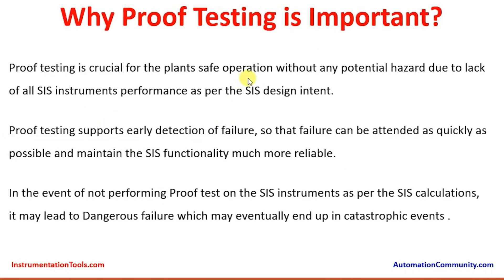Why is proof testing important? Proof testing is crucial for the plant's safe operation without any potential hazard due to lack of Safety Instrumented System performance as per the SIS design intent. Proof testing supports early detection of failure so that failure can be attended to as quickly as possible and the SIS functionality maintained much more reliably.